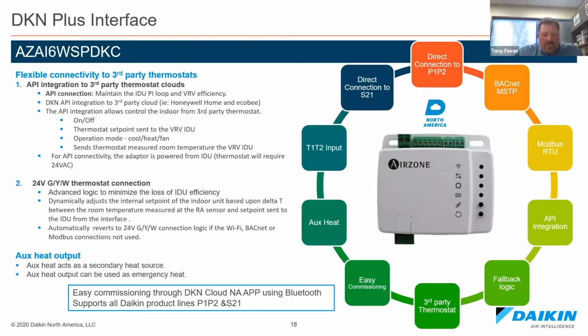When the other manufacturers allowed the use of, say, third-party thermostats to work with their VRF systems, one of the things that happened is it instantly made the electronic expansion valve go to either fully open or fully closed.